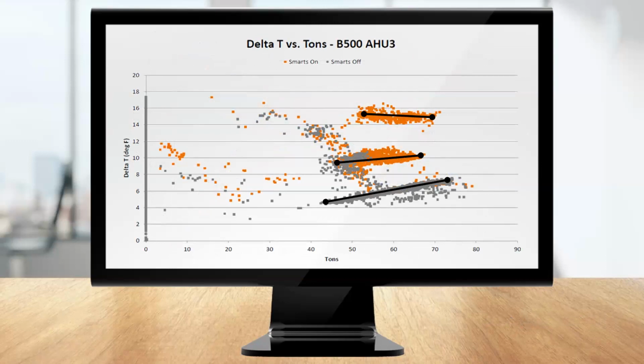What we have here is a valve that was placed into 3 different control or limiting methods. Smart valves can be put into 3 modes, which are position control, which is a standard control valve operation, flow control, like an electronic pressure independent valve, or delta T management in that smart valve mode. So let's evaluate the performance of each of these at a given load of 60 tons. So at 60 tons, we utilize 240 GPM to achieve that 60 tons.